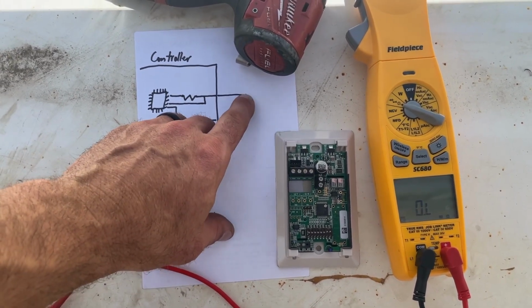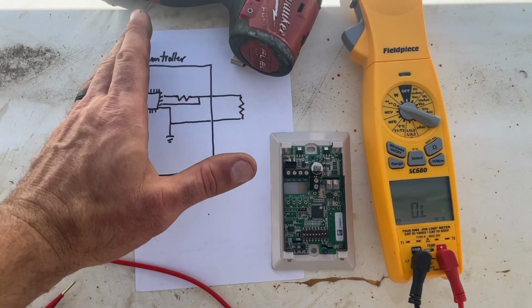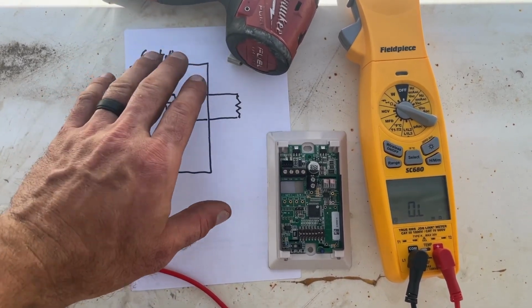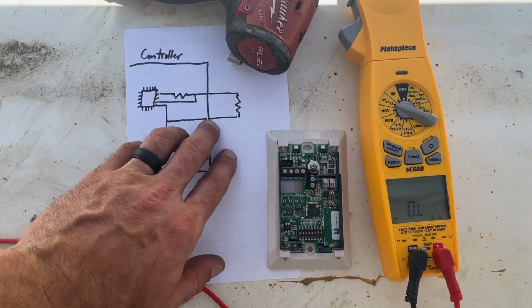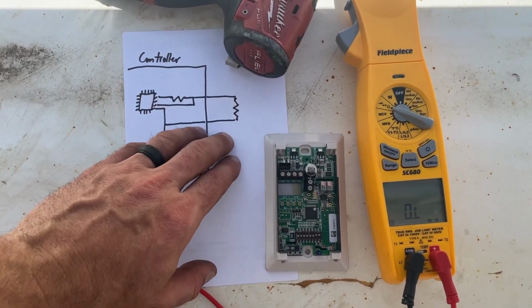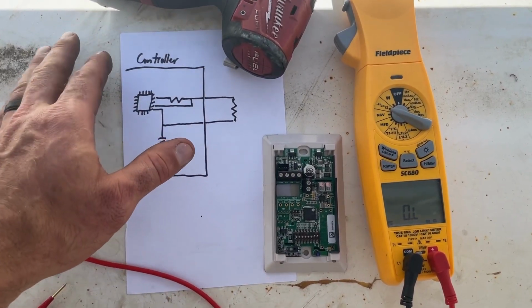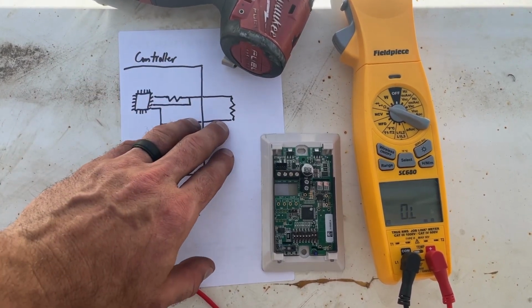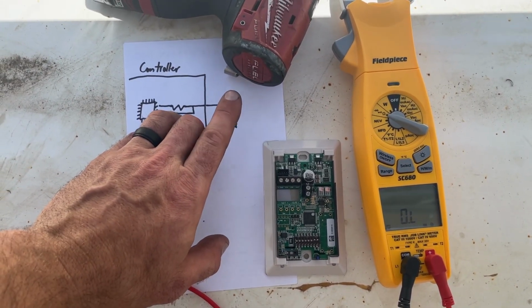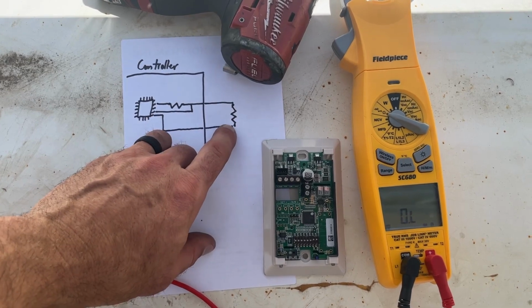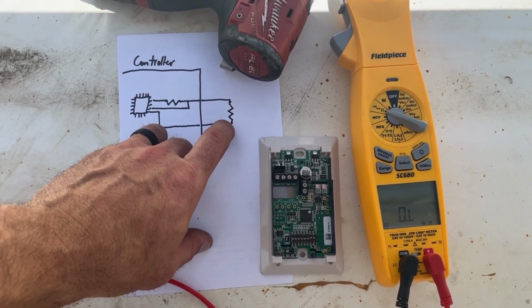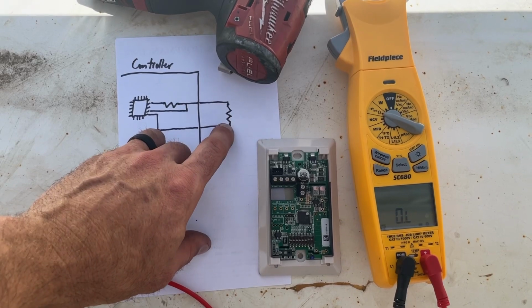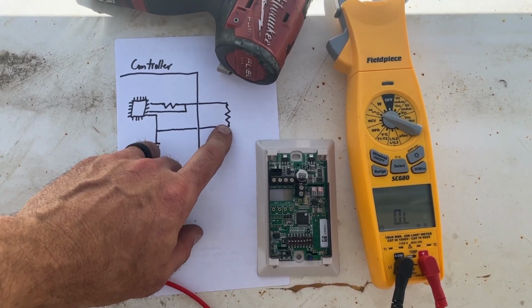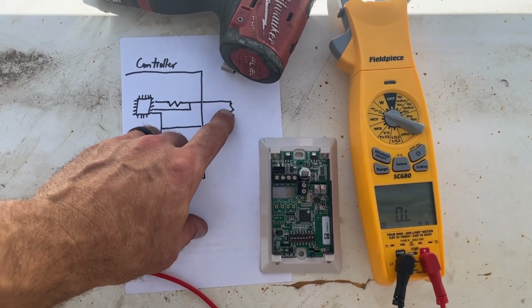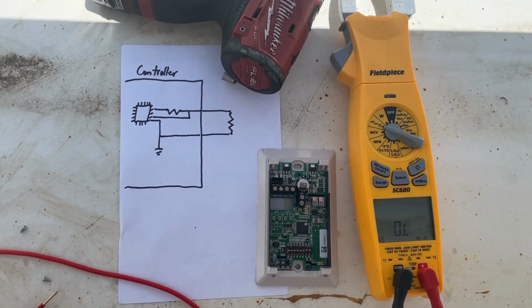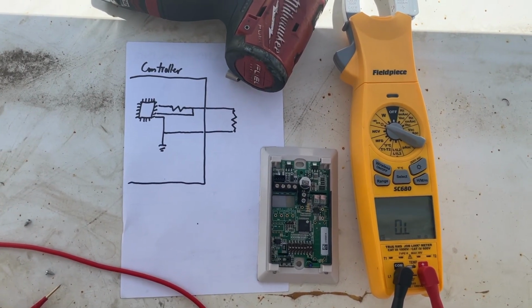Now, by the way, 10K thermistors are extremely common in HVAC. Daikin uses 20s except for the discharge. But anyway, when you're talking about 10 or 20 or things like that, what that means is that at 25 degrees Celsius, which is 77 Fahrenheit, this thermistor will read 10,000 ohms. If it's a 20K thermistor, it will read 20,000 ohms at 25C, and that will help you in your troubleshooting.